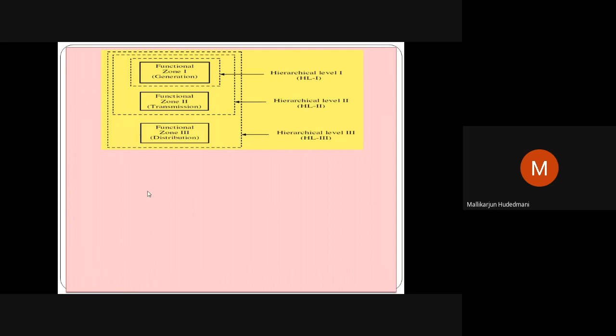I was speaking about adequacy measure being done in 3 ways. One is the inner rectangle, this rectangle, functional zone 1 itself. This is only generation, hierarchical level 1. Then if I club transmission and generation, zone 1 and zone 2, it becomes the next triangle, the dotted rectangle, that becomes hierarchical level 2, HL2. Then if I superimpose this with distribution, together it is the outer dotted rectangle, that becomes hierarchical level 3, HL3.